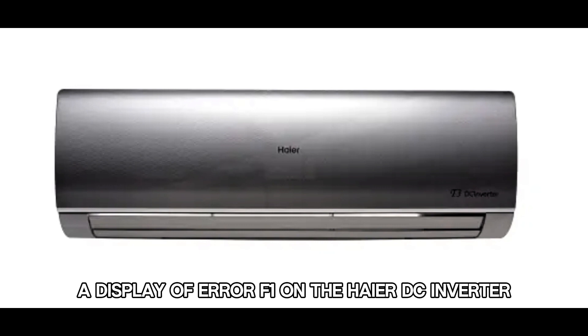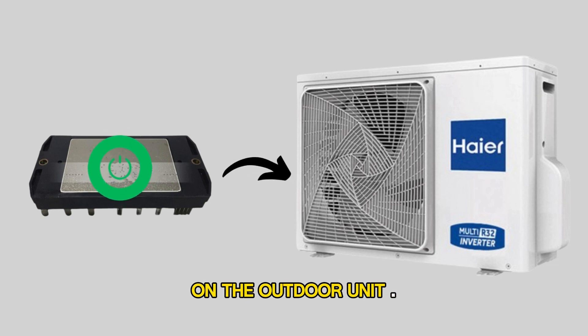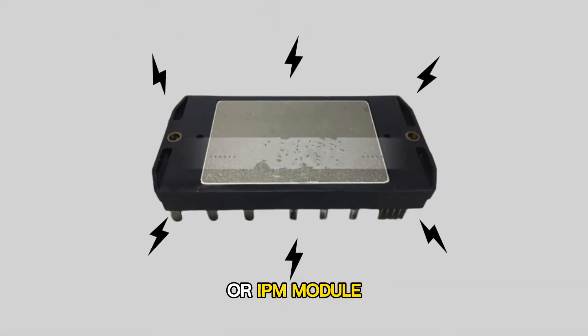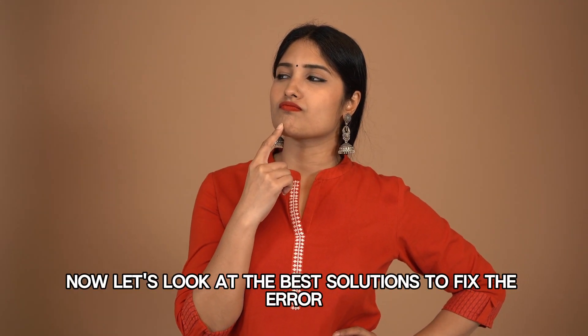A display of Error F1 on the Haier DC inverter indicates activation of the IPM protection on the outdoor unit. This is the most common cause of the error code — a faulty compressor or IPM module. Now let's look at the best solutions to fix the error.